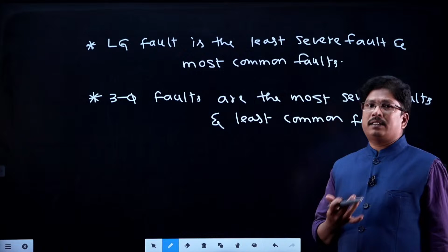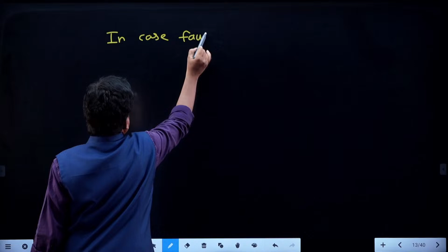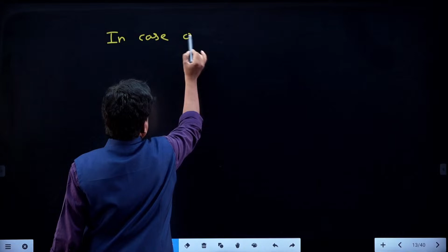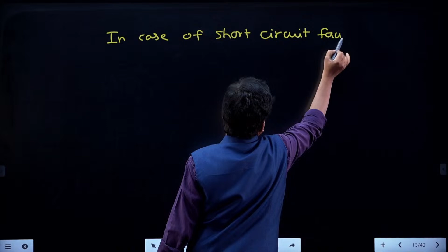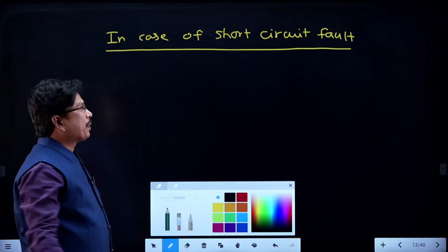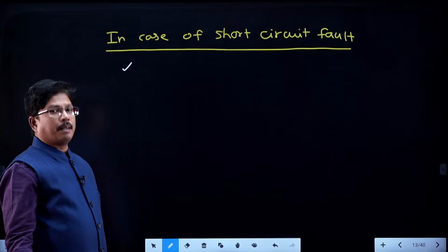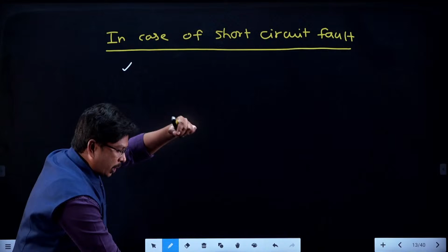Right, students? This is some clarity about the faults. And how can I characterize the short circuit fault? You can see the characteristic of the short circuit fault. Students, in case of the short circuit fault, the voltage will be very low. It may become nearly 0, sometimes may not be 0, depending upon the fault impedance. Suppose if the line is directly grounded, that is a dead short circuit fault called a bolted fault. So remember, students, bolted fault means dead short circuit fault, so the voltage will become 0.